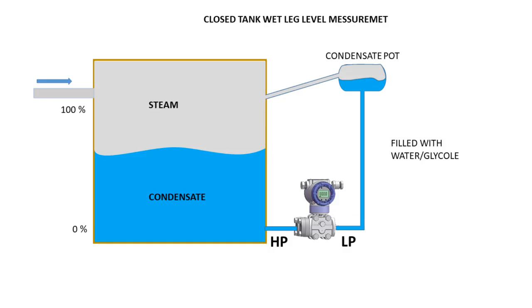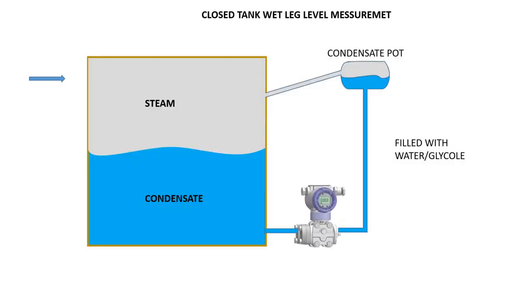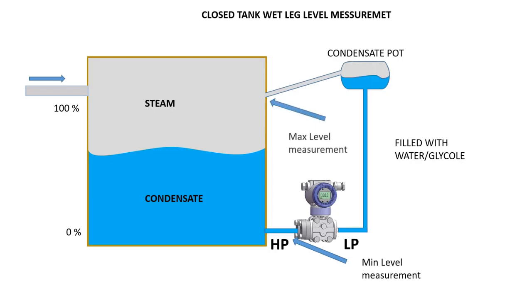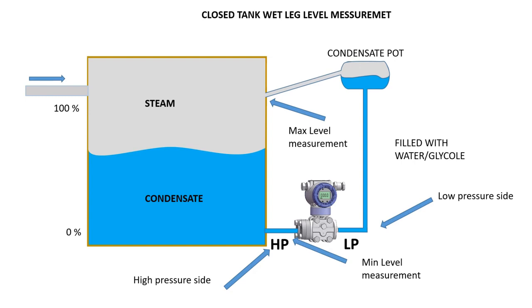To avoid that, we use a condensate pot. One side of the condensate pot is connected to the low side impulse line and filled with water, and the other end connects to the tank top. So the steam will directly act on the condensate pot and the pressure transfers to the low pressure side of the level transmitter. The high pressure side of the transmitter also receives pressure from the condensate water. If we do not use a condensate pot, the steam condensate causes the low side pressure to keep changing, affecting the calibration of the transmitter. The condensate pot helps keep the water level the same and transfers the steam pressure.